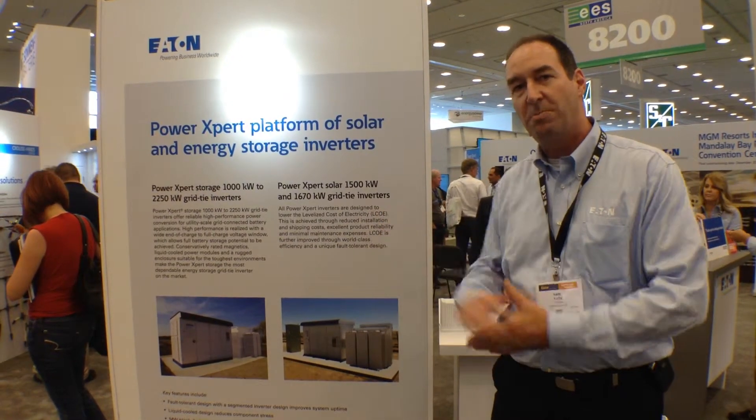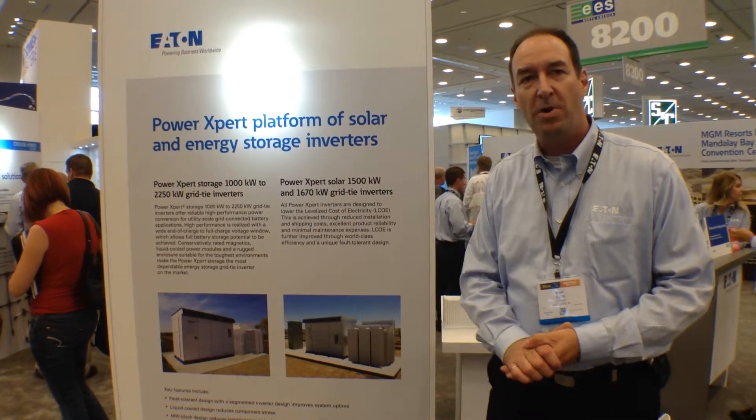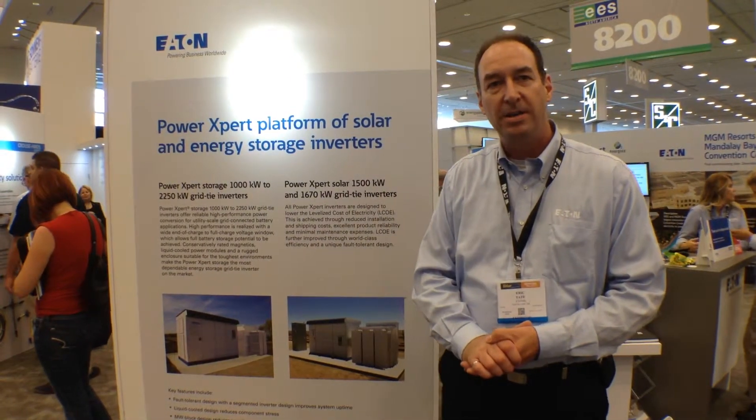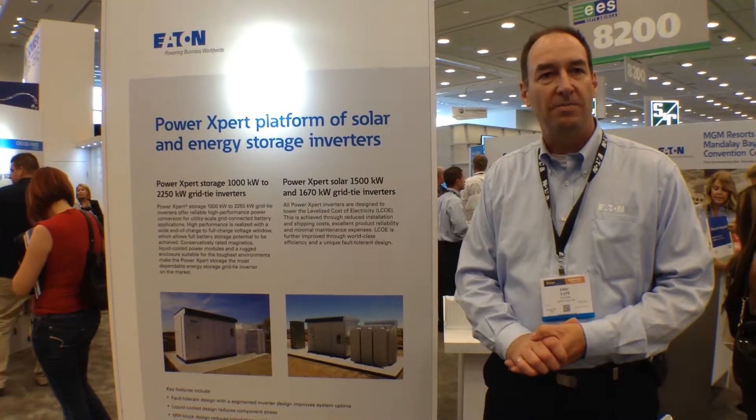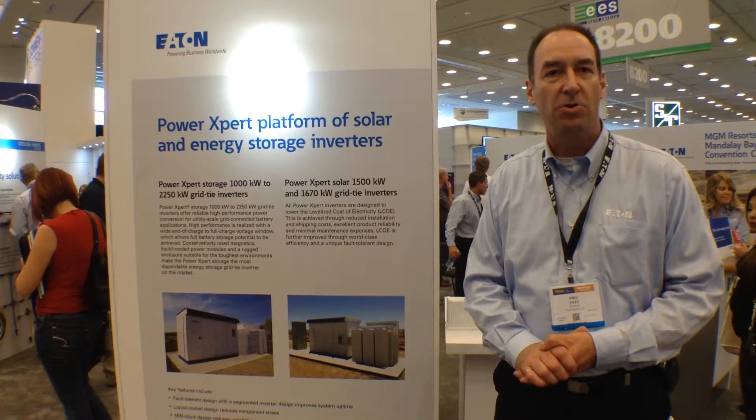To look at our solar product line, we put in the utility scale on the market — 1.5, 1.67 megawatt. It's a very robust inverter design. We use liquid cooling for the Power Xpert products. It's a self-contained outdoor unit. We have what we think is a fairly unique coupling arrangement between our inverters and the medium voltage step-up transformers.